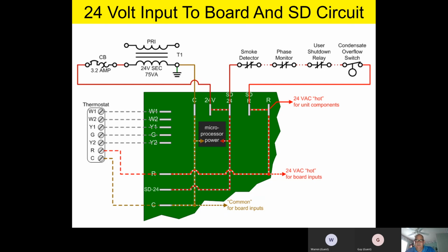The other thing is that if you're getting erratic operation on a gas pack, make sure you have really good grounding. And if it's not a gas pack, make sure that all your limits are closed and you have that red jumper there, or you've got a dry set of contacts in that SD24 and SDR. So those are just a couple little things that we've found in the field, that if you're getting that SD24 fault, check grounding. Make sure you got a good solid connection there between SD24 and SDR. And then finally, make sure you've got your 24 volts on your microprocessor and so on. So just keep that in mind. It's a safety circuit, and it has to be closed in order for the unit to work.